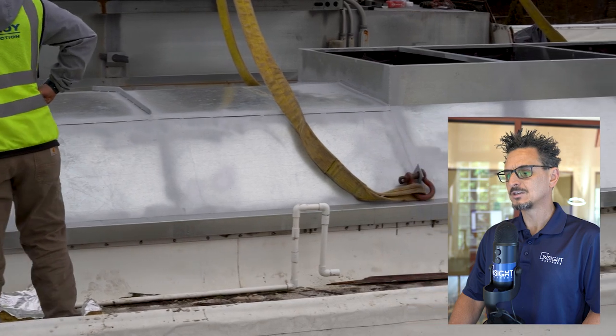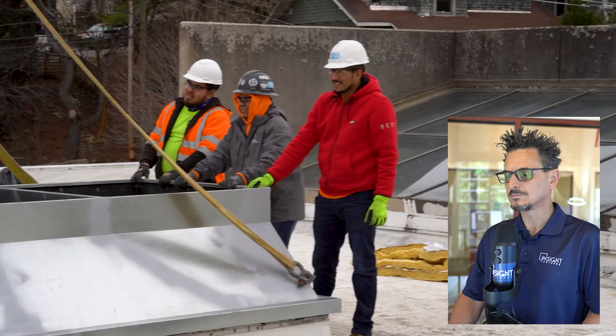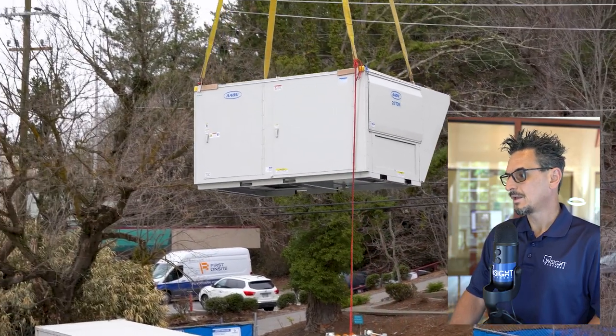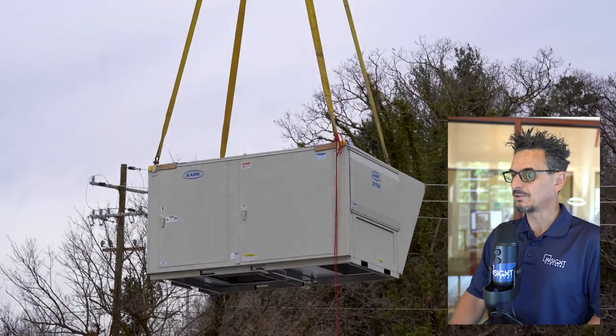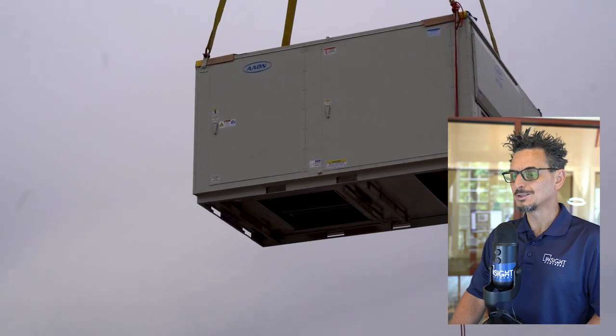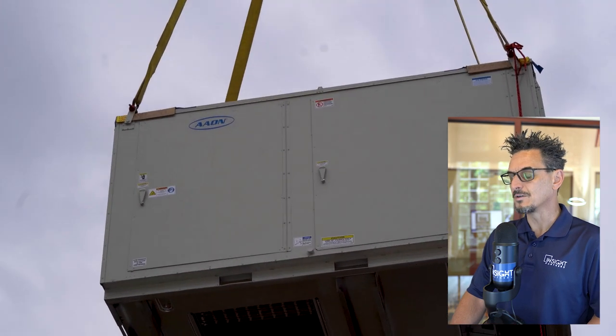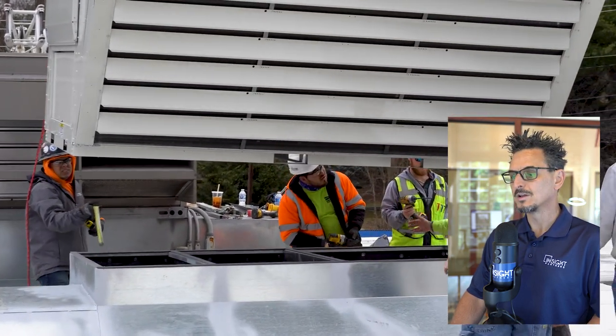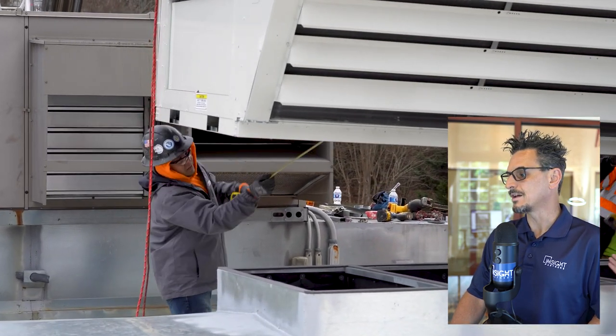Here's a nice shot of the adapter curb in place on the existing roof curb. Now it's finally time for the AAON unit — here comes the AAON. This is an RN-20, as has been mentioned a few times; this is what's called a C cabinet. We're craning this over there, and again this is another time where it gets a little nerve-wracking to make sure it all fits up. We know the adapter curb on the base fits on the existing curb. Now we need to make sure that the curb on the top fits on the supply and return of the AAON unit.